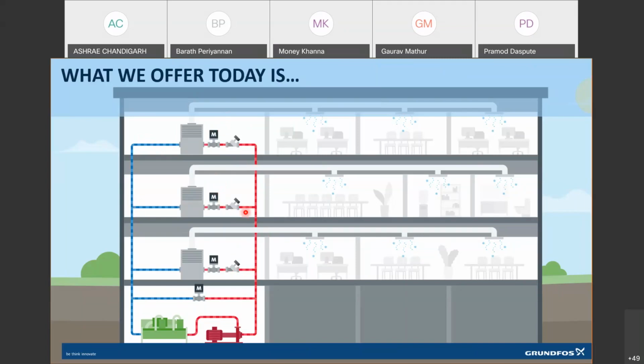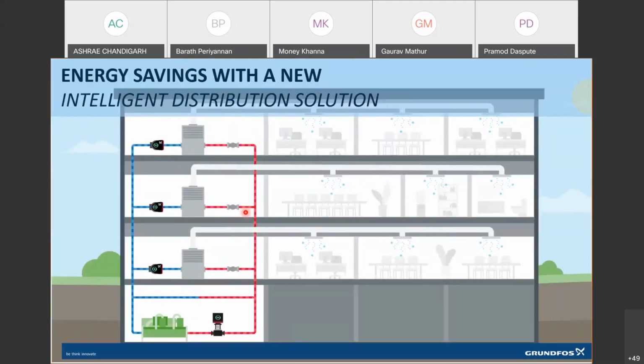It can be with the help of manual or automatic balancing. There are various ways you do that. But essentially, what you're doing is generating pressure and then killing it. What we see in a distributed pumping system is that we have pumps, as you can see, connected to individual AHUs. And we have a pump which caters to the production loop, or the chilled water production, which is separate from the pumps on the secondary side. So this is one of the changes which happens.